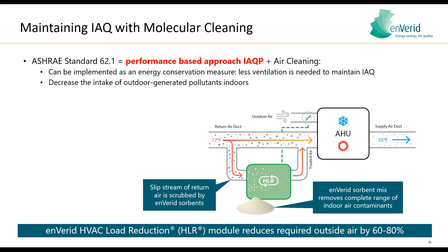So how do we implement this solution? We take a part of the return air stream, it can be a plenum or it can be ducted, we clean it, and we put it back into the return air. So we're not cleaning outdoor air, we're cleaning only return air. By doing so, we can decrease outside air by as much as 60 to 80%, while keeping the building positively pressurized, employing these HLR modules, which stands for HVAC Load Reduction modules.